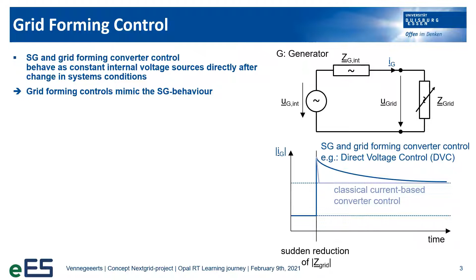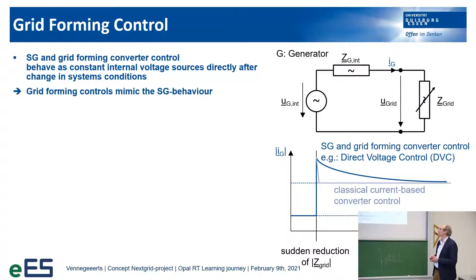And this is what the grid forming control also does. A classical control of converters, like a current-based converter control, will go very fast to the new stationary point. It seems favorable. However, this brings very high dynamics in the network, since the synchronous generator always tries, by this retarding of the internal voltage, to level out the changes that have been produced by external influences. That's what grid forming converter control tries to mimic. One of them is the so-called direct voltage control, DVC, which has been developed at our institute.